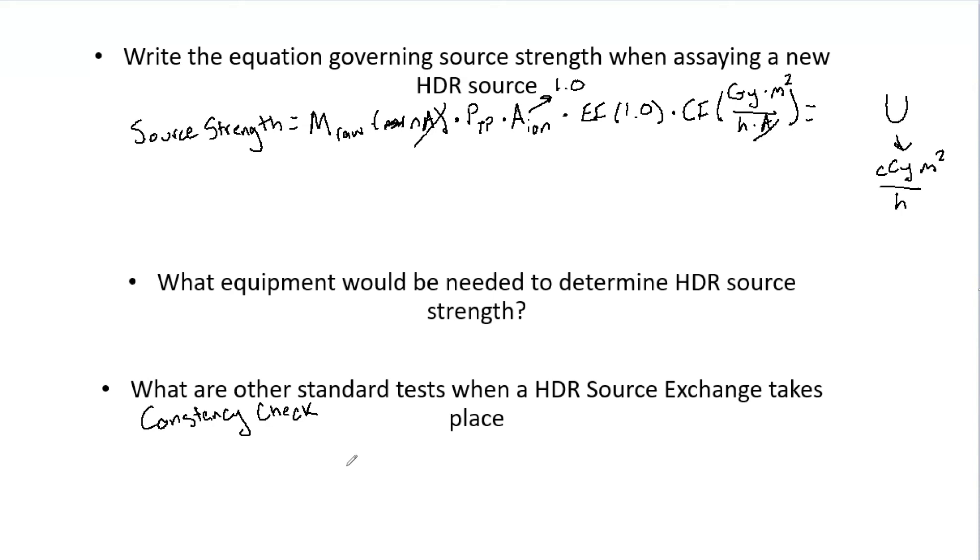So essentially, you have an old source that you know what the activity is. So by setting up your chamber and electrometer, verifying that you're going to get the same source strength when you already know what it is, you can say my chamber, my electrometer, my setup works, that those things are working correctly. And when I get my new source, if that activity is off for some reason, it's not my equipment, it's something with the source. So that is one thing you definitely have to do.